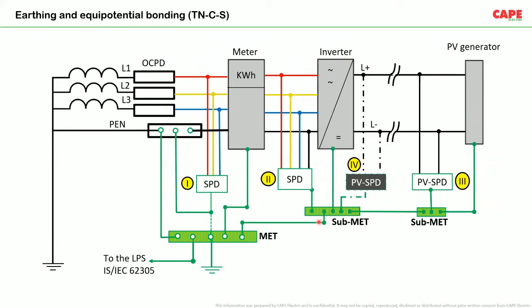Then from the sub MET, the connection shall come to the main equipotential earth bus bar of the building. Let us say this is applicable for a rooftop installation. You have the kilowatt hour meter or the mains incoming, and near the mains incoming you have the MET. From the MET, the protective conductor shall be extended to the inverter. Further, it has to be extended to the frame of the solar PV installation. This is how the earthing of a solar PV installation shall be made.